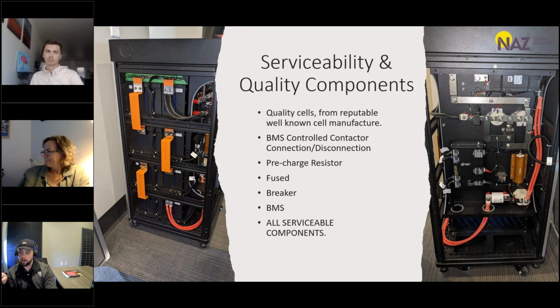That's very important. At the very bottom you can see it's fused, a big 400 amp replaceable fuse. If you dead short this battery and the BMS can't react fast enough, or you make a mistake, people make mistakes, the fuse can blow and protect the system, because this battery can deliver mind-blowing amounts of current. It's rated at 9 kilowatts and 12 kilowatts, but that's to prolong the life of the battery, not what it's limited to. If you hook to these cells and try something stupid, it'll do it, but that fuse helps protect it.